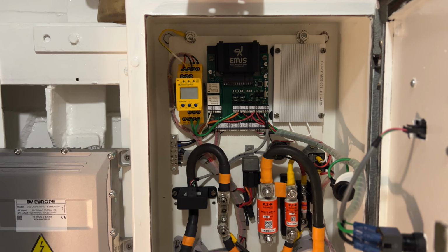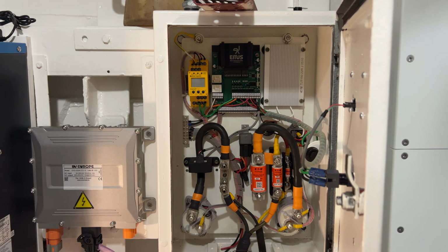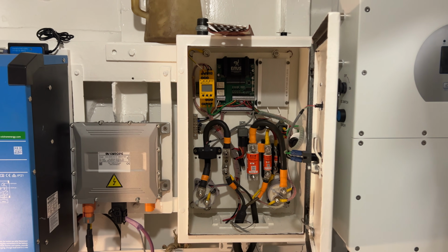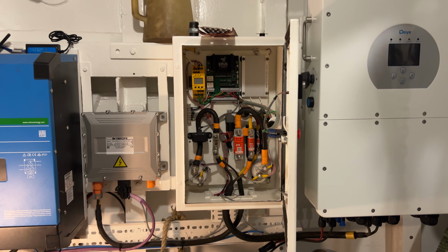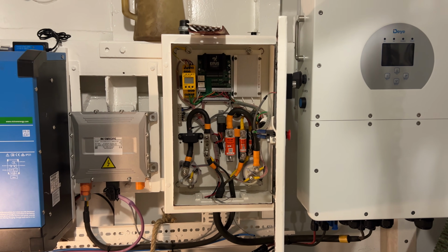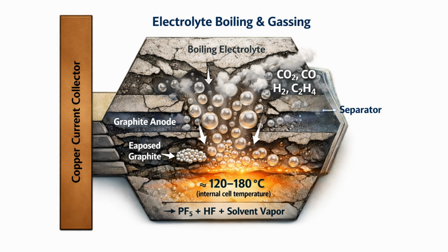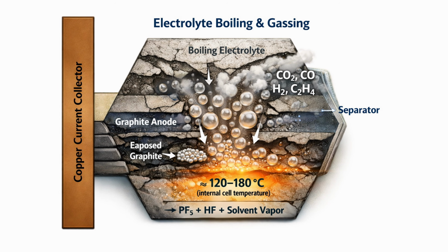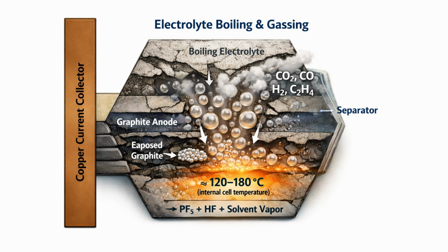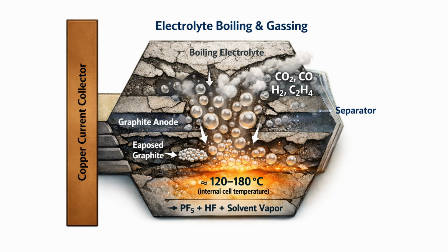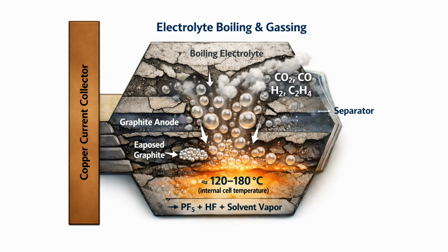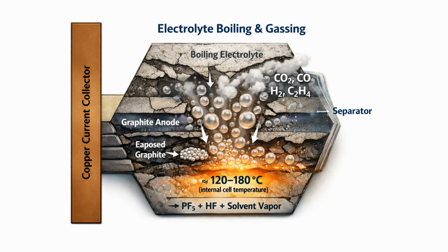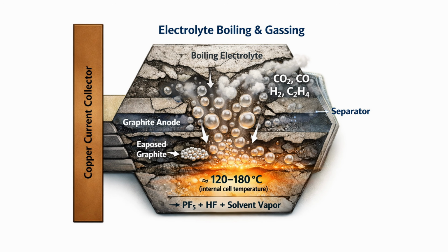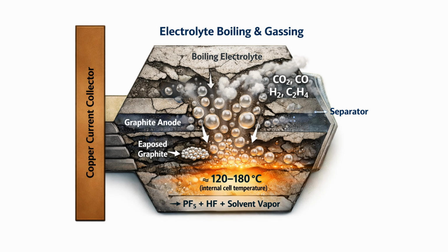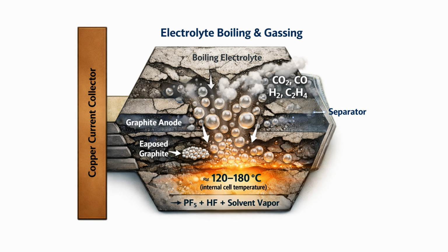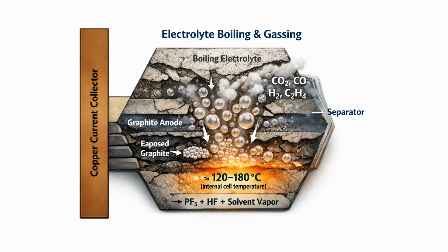And in this stage the BMS already detects that something is wrong and it will open the high voltage contactors. But the module itself doesn't heat up much yet. The second stage is gassing or venting. At a cell temperature of around 120 to 180 degrees, the electrolyte starts to boil. Pressure rises and now the temperature of the module casing starts to increase. The temperature in our battery box rises with it, typically up to around 80 degrees. This stage can take tens of seconds to minutes.